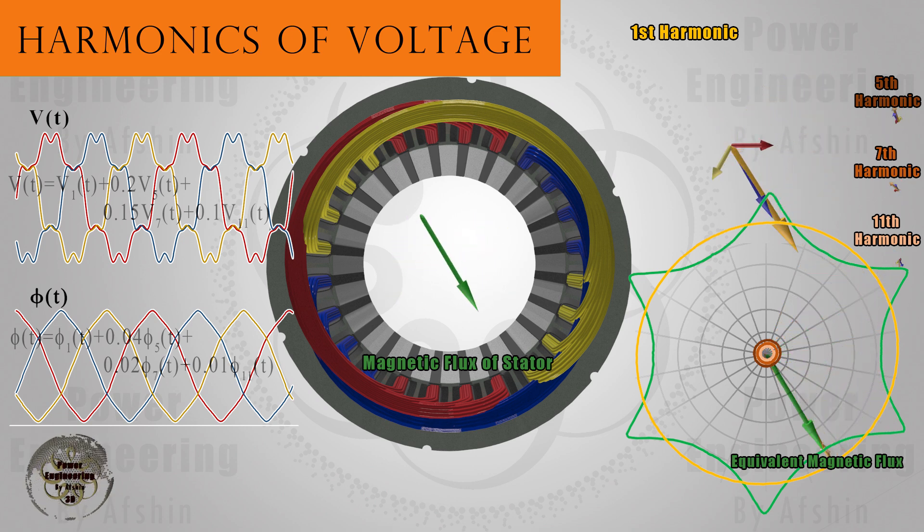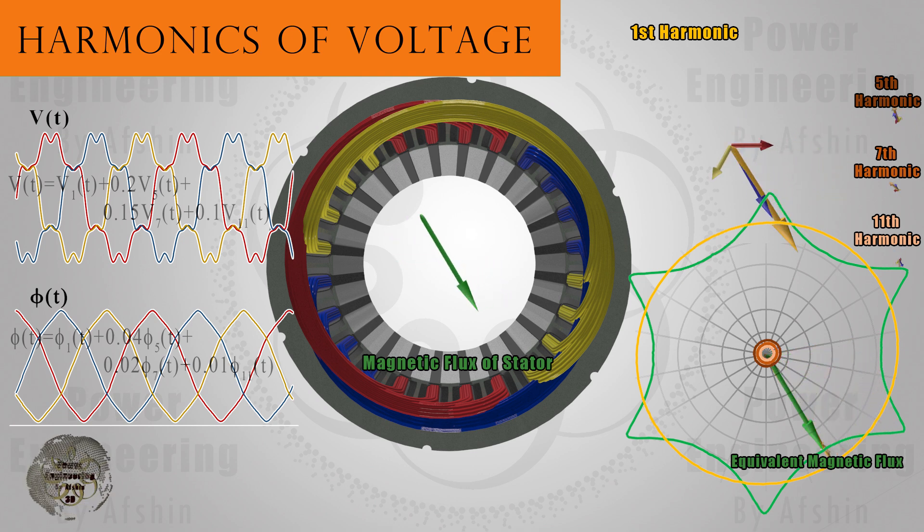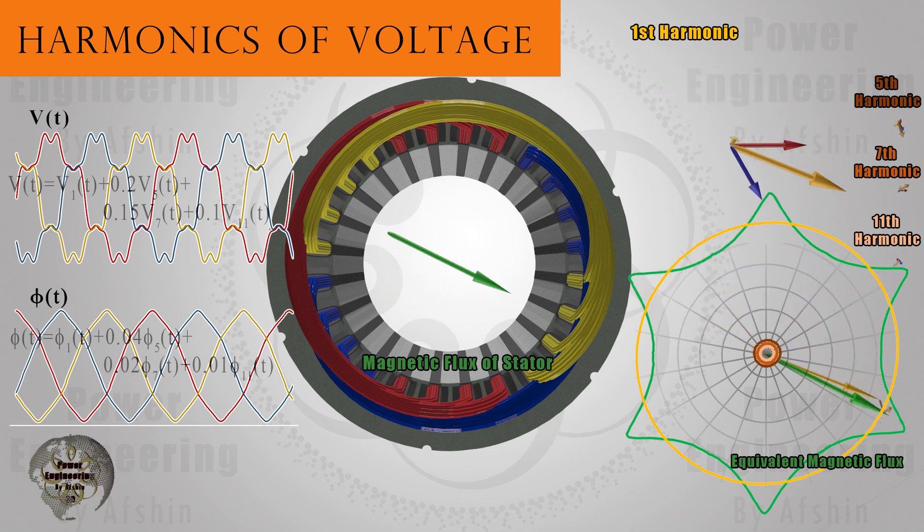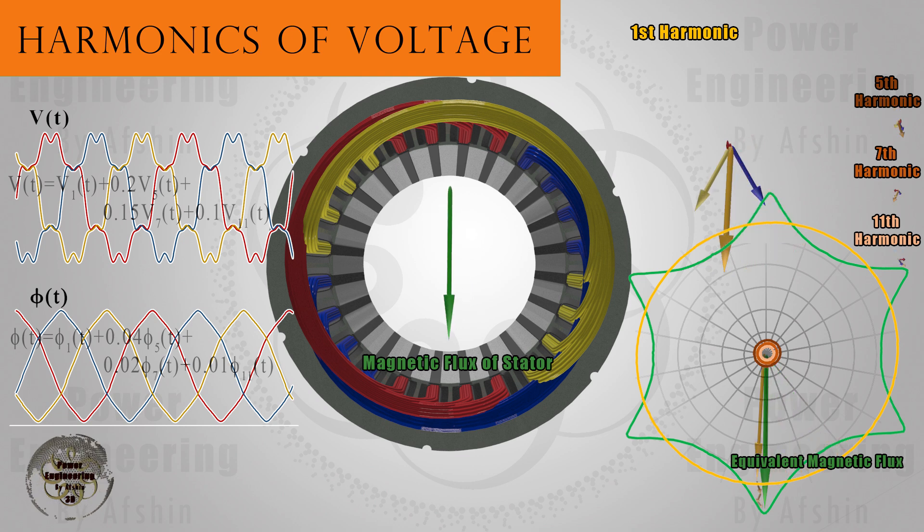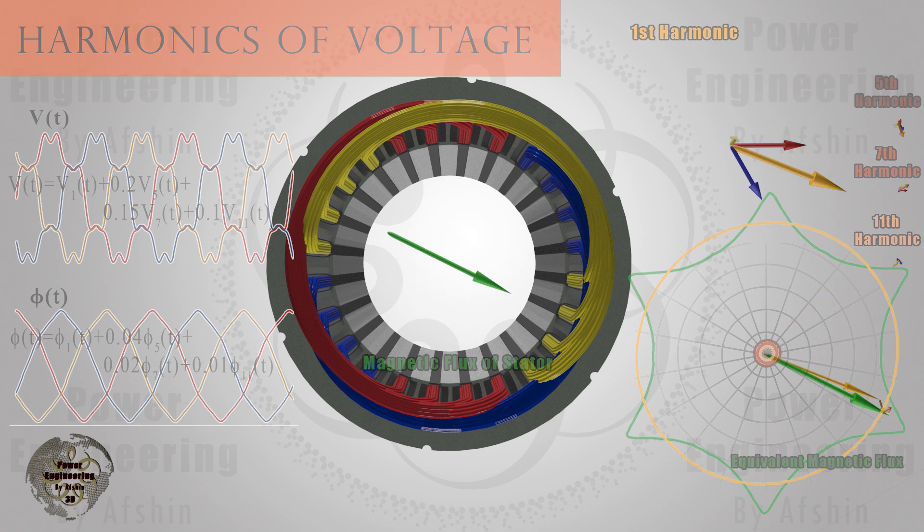On the left side, you can see the amplitude curves of the rotational magnetic field, voltages, and magnetic fluxes. On the right side, you can observe the magnetic field corresponding to each harmonic. The presence of harmonics leads to increased vibration, resistance due to skin effect, and iron and copper losses in the motor, thereby reducing its efficiency. Moreover, it may also cause saturation in the stator.